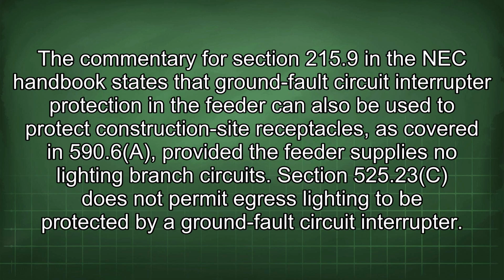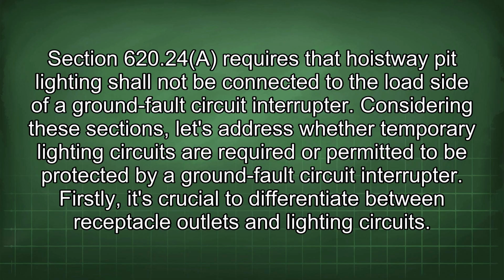The commentary for Section 215.9 in the NEC handbook states that ground fault circuit interrupter protection in the feeder can also be used to protect construction site receptacles as covered in 590.6(A), provided the feeder supplies no lighting branch circuits. Section 525.23(C) does not permit egress lighting to be protected by a ground fault circuit interrupter. Section 620.24 requires that hoistway pit lighting shall not be connected to the load side of a ground fault circuit interrupter.